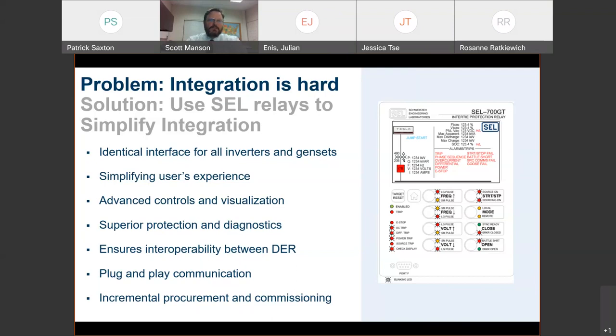The inertias are low, the responses are fast, the faults are variable, inverters are, well, unpredictable, and everything's happening at a time frame that is orders of magnitude sometimes faster than the traditional power system. And so this integration is hard. And so the number one tool that I use, the number one tool that most people I work with use, is an SEL relay, or the relay on every inverter, to simplify.